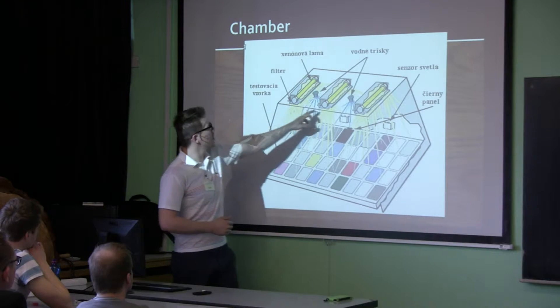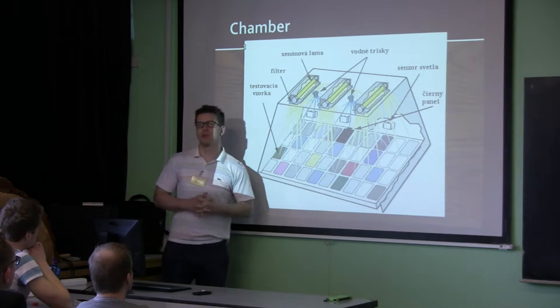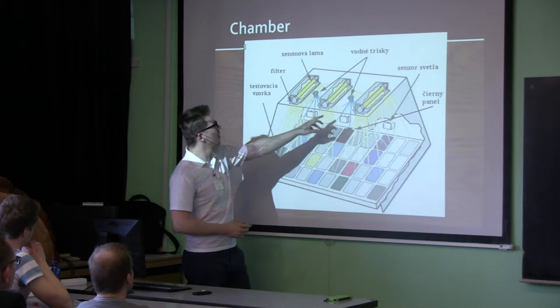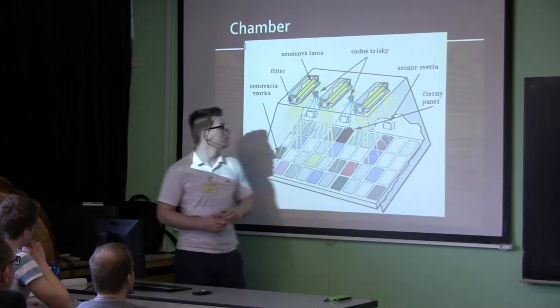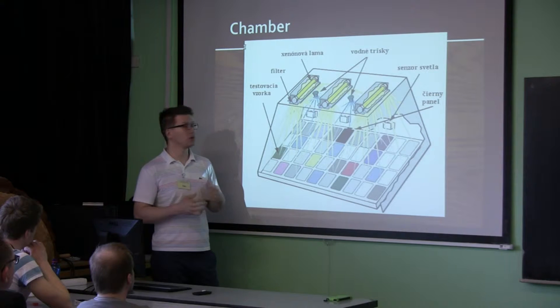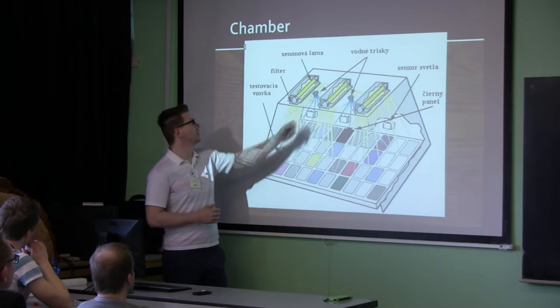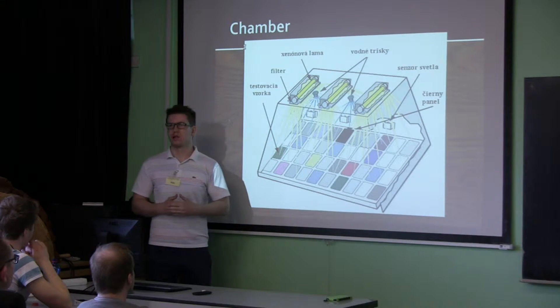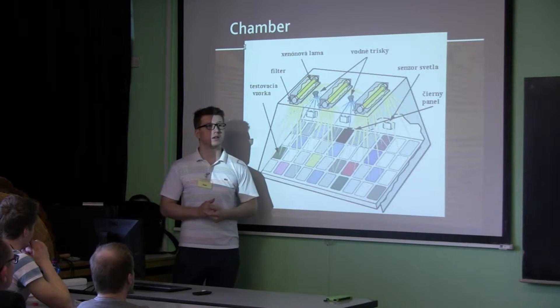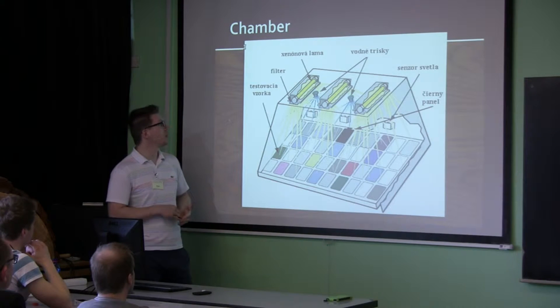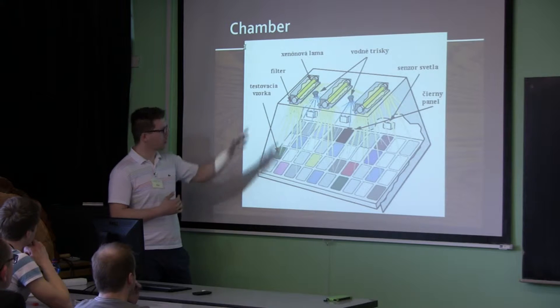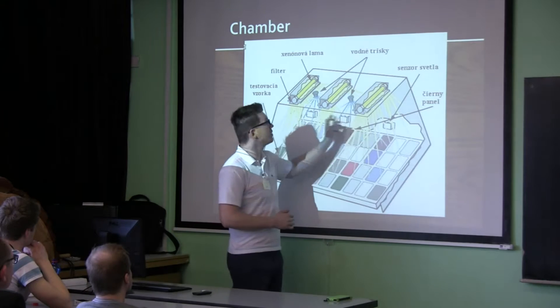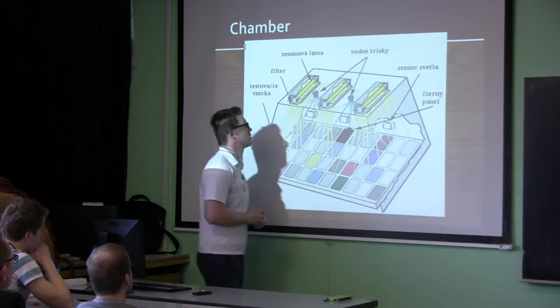This is the place where the filters are. When we change the program, we can choose the program for interior or exterior. This is the place where we put the glasses — we can put interior glass, which reproduces the sunlight as it comes through a window, or exterior glass. The difference is that interior glass, like window glass, does not allow as many UV waves to reach the surface of the wood.